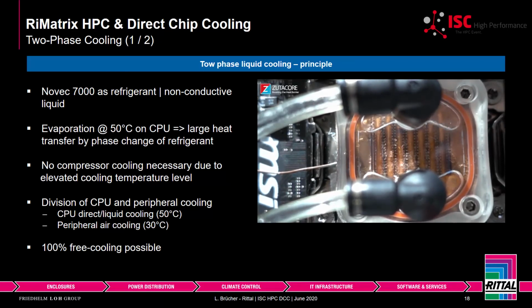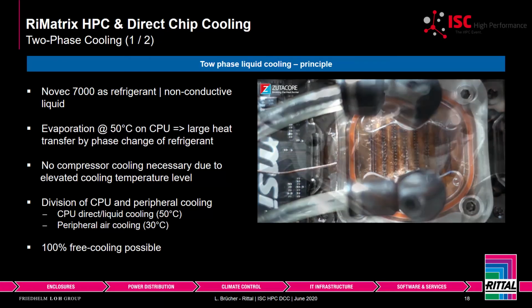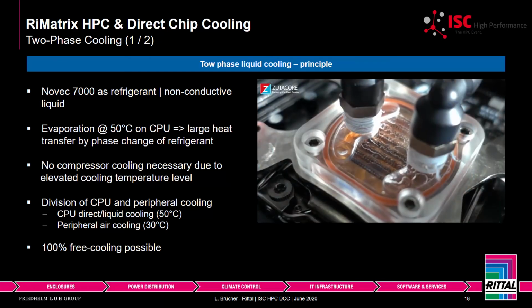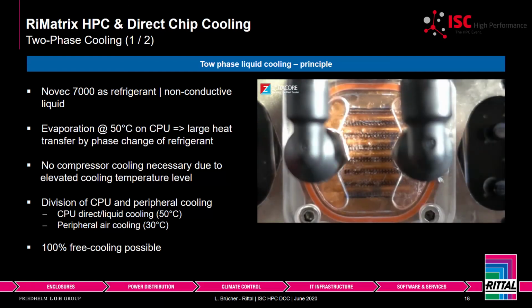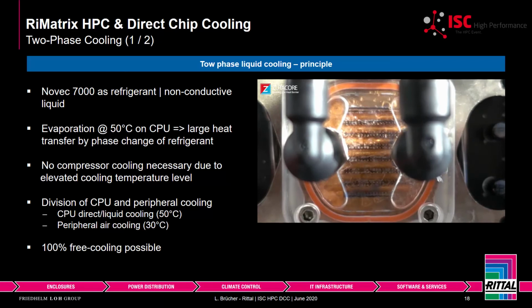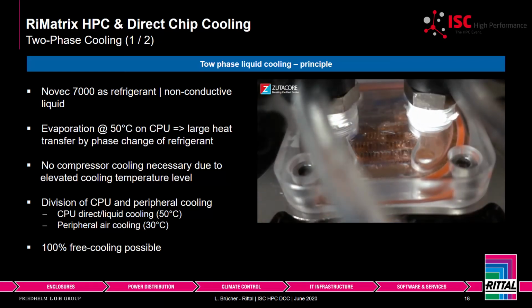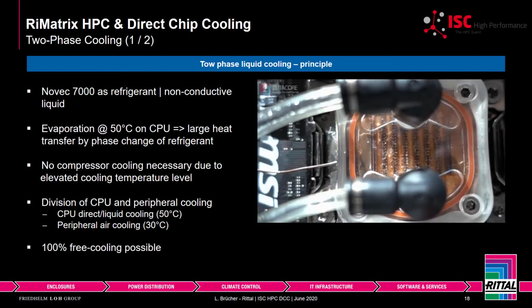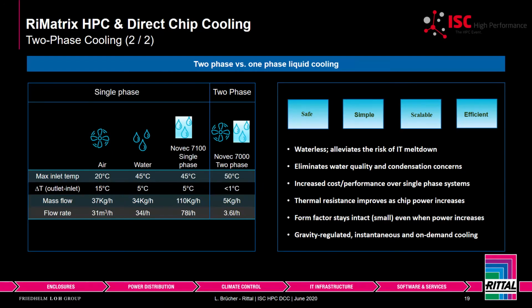But in addition to this, since it's a dual phase technology, it's using the latent energy of the liquid, which means at 50 degrees, it's evaporating. So you're creating a very constant cooling temperature at the chip, and not only constant, but also quite high. This enables a very optimal operational temperature for the processors. Some companies, we know, not us, are testing if this will enable overclocking of the chips. You also don't need compressors because the inlet temperature is high.